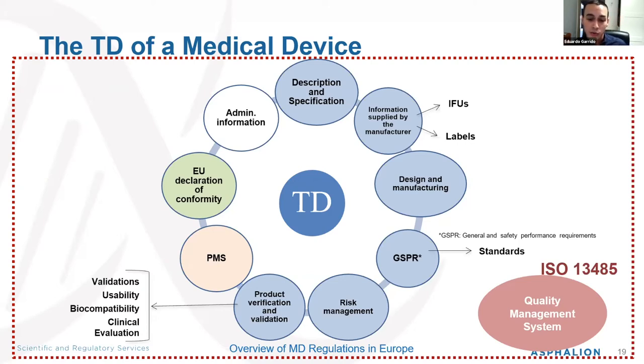You will also have to perform a risk management task on your device — you need a risk management plan in place. Then you also have to include all the testing you've done: validations, usability data, biocompatibility data, and also very important, clinical evaluation and clinical data, which has to be provided and included in your technical documentation.